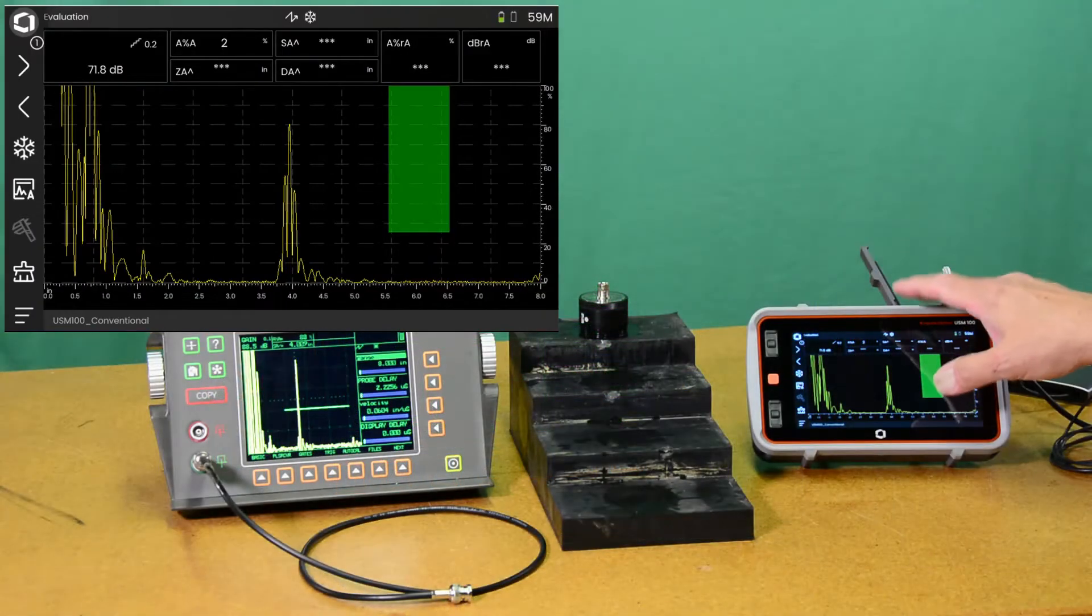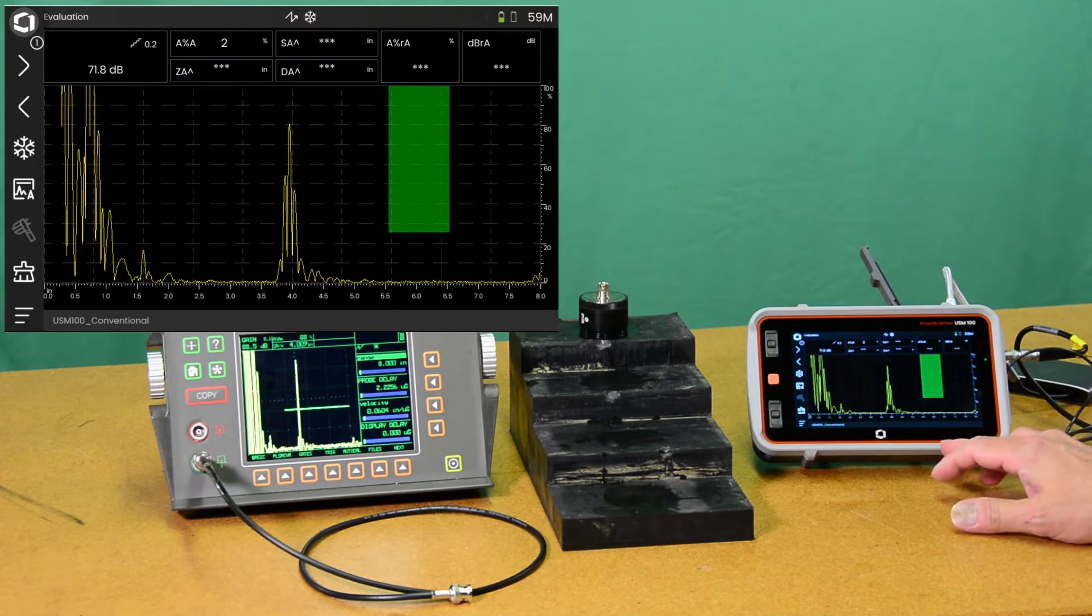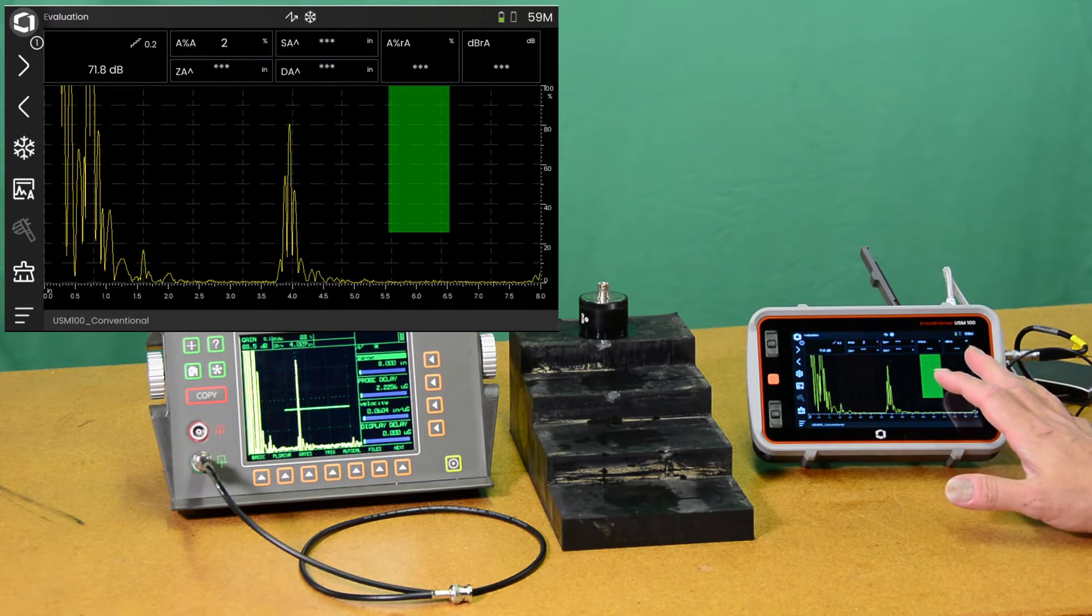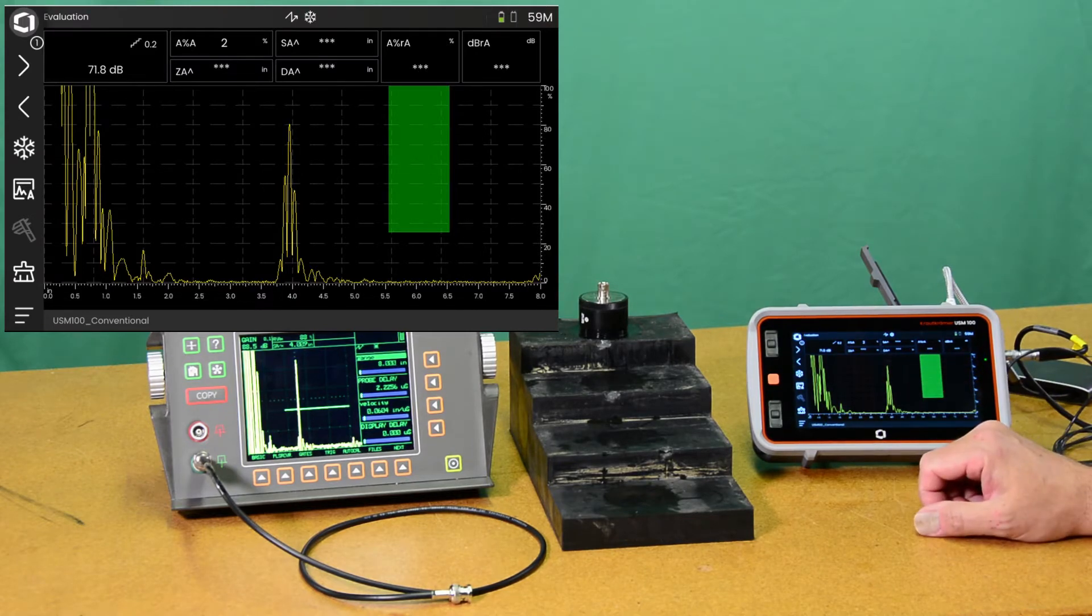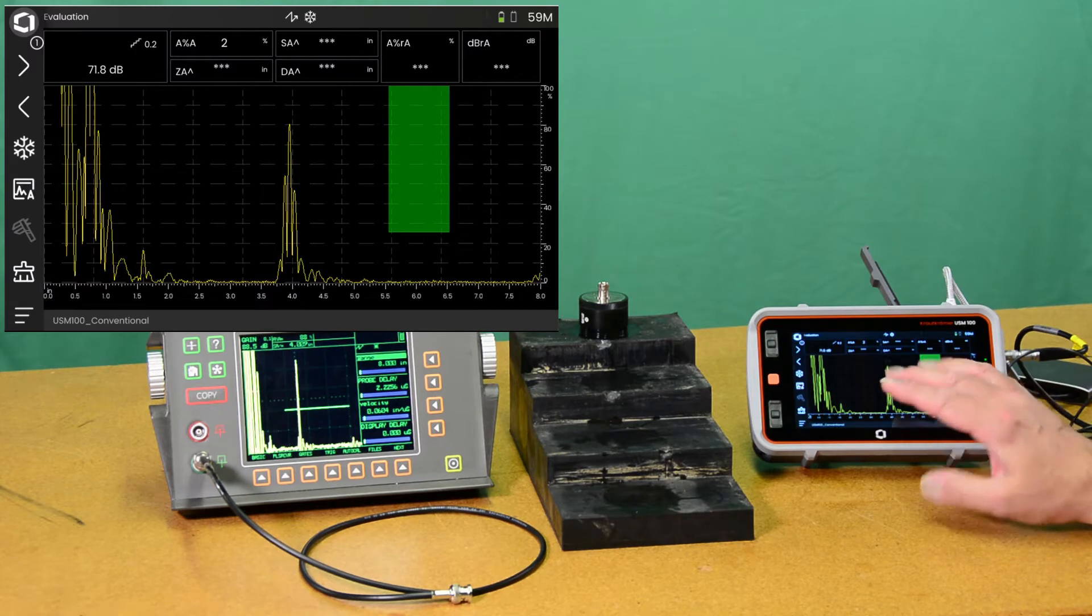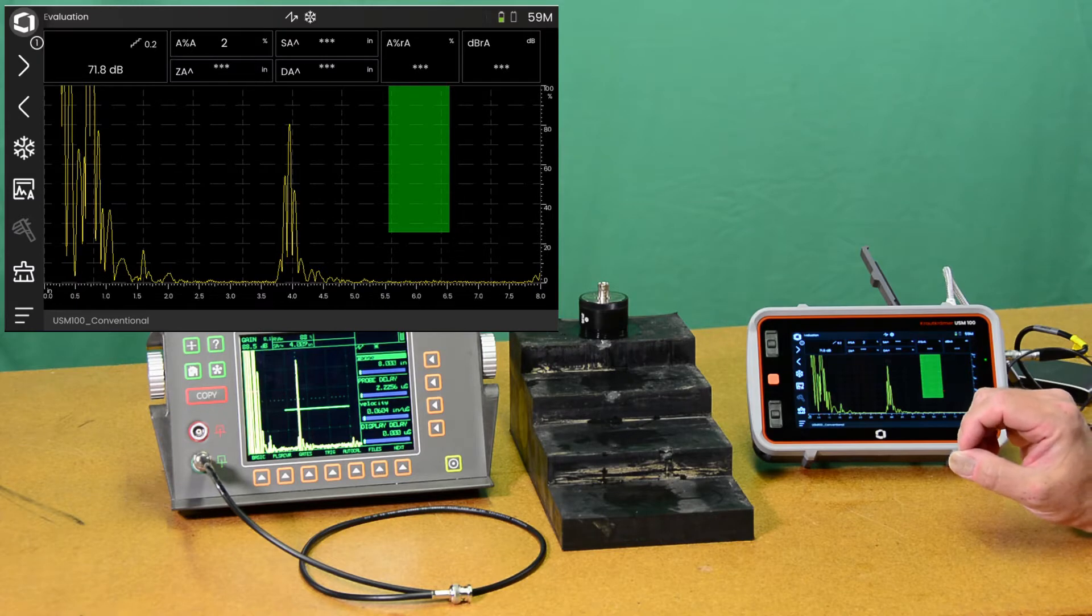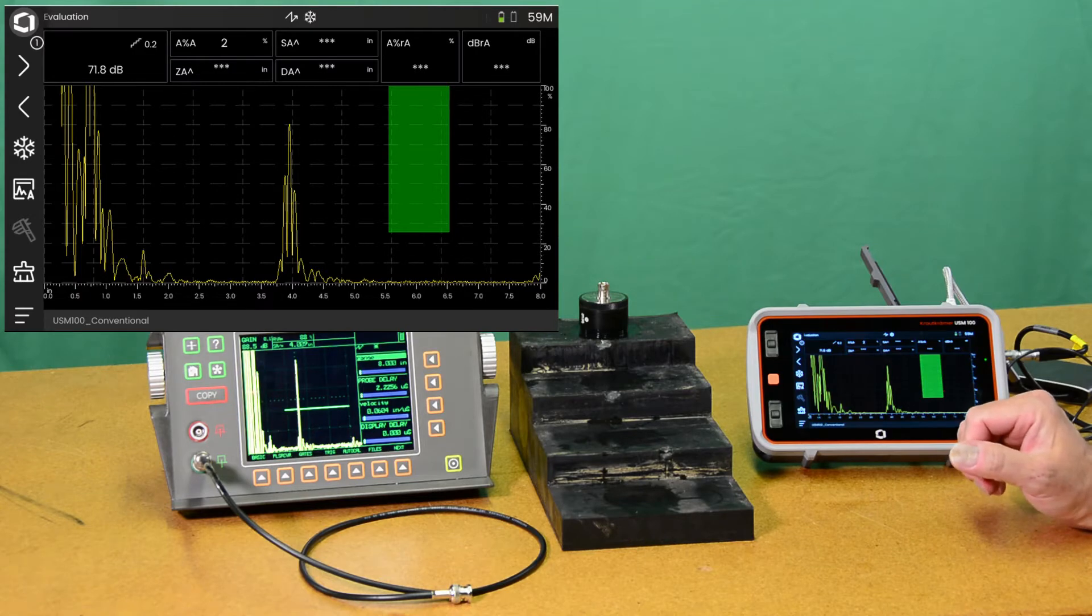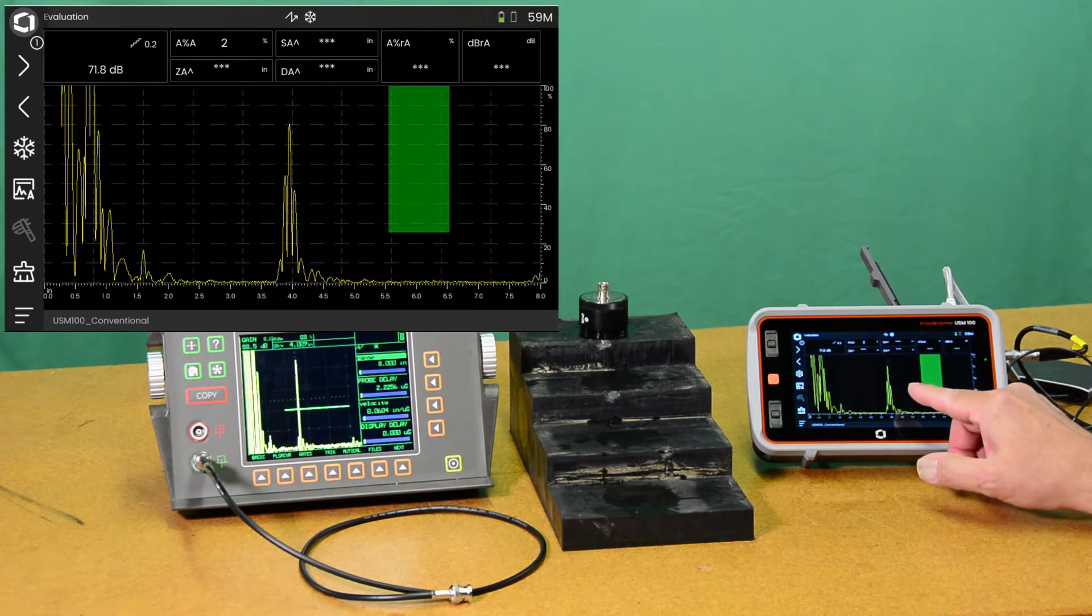Over here on the USM-100 I have also optimized setup for that. I have the display frozen again with 4 inch echo. Gain here is set to 71 dB. Even though the pulsar voltage doesn't go quite as high, it tops out at 350 volts as opposed to 450, that's only a dB or two difference to start with.